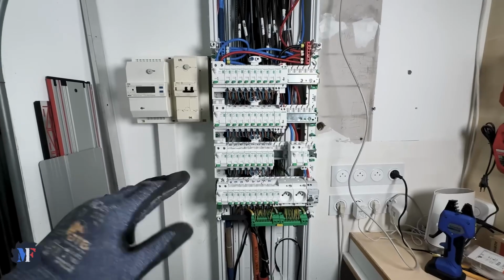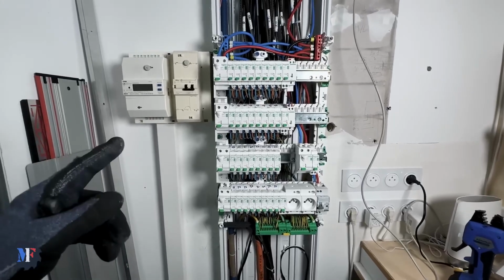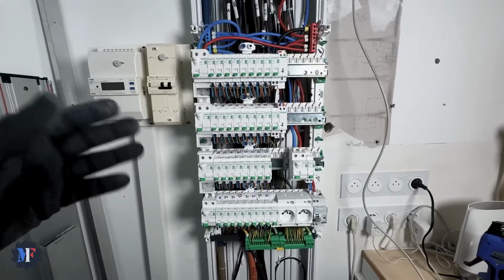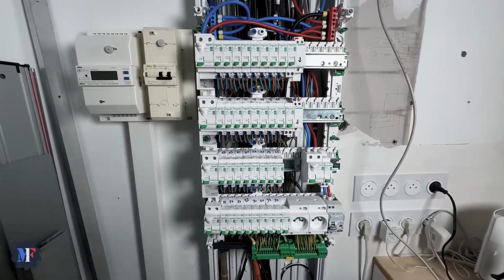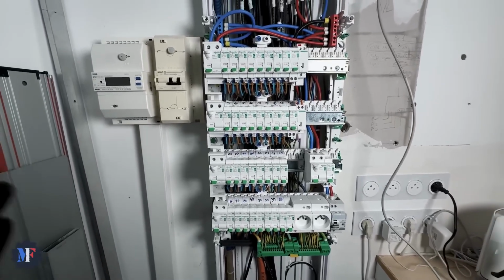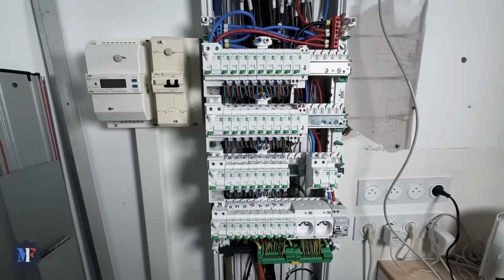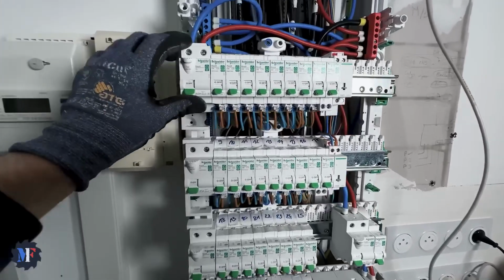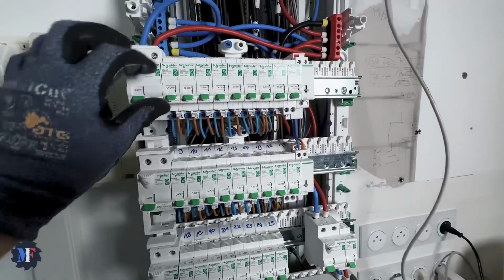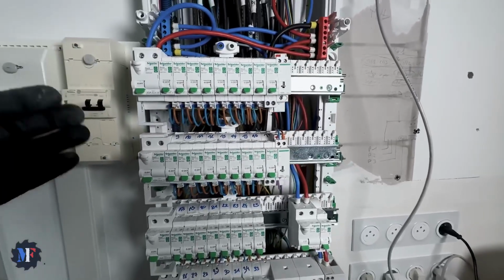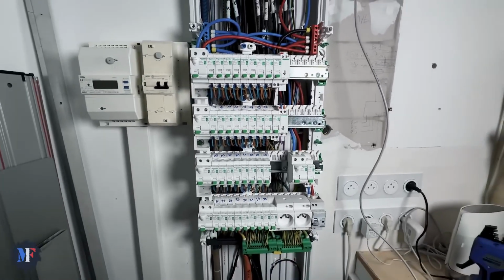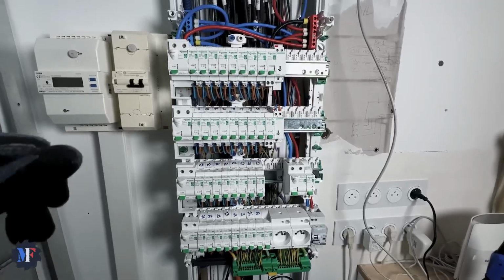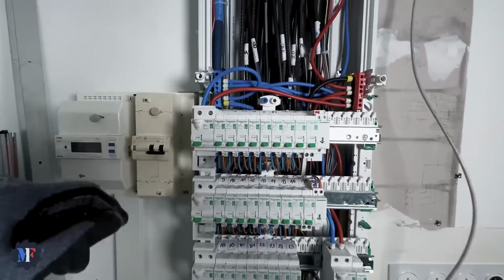The panel is finished. All that's left is to turn on the power, but of course we'll check that everything works. Instead of powering everything on and risking a trip, you'll wonder where the problem is coming from. The ideal way is to turn on one residual current device and then each circuit breaker. And if it trips, that means there's a wiring problem. We'll turn on each switch and circuit breaker to check everything, but first, a quick recap.